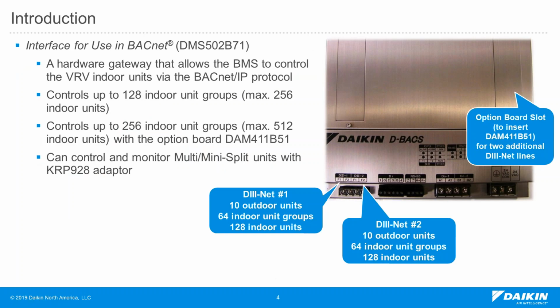The interface for use in BACnet, the BACnet interface, allows the BMS to control the VRV system by commanding the indoor unit points. The gateway itself can control two DIII-Net systems. For each DIII-Net system, you can control up to 10 outdoor units, 64 indoor unit groups, and a maximum of 128 indoor units if you group some of the indoor units together. So it can control two DIII-Net systems, which means that one gateway can control up to 128 indoor unit groups, and that is a maximum of 256 indoor units.